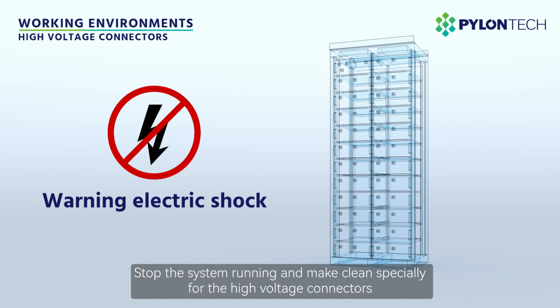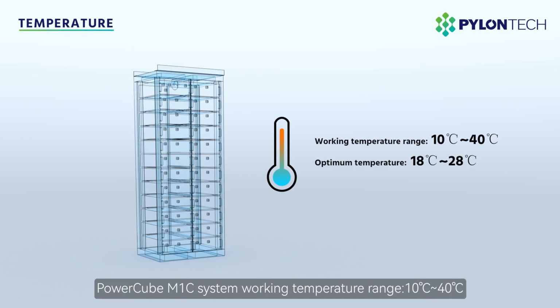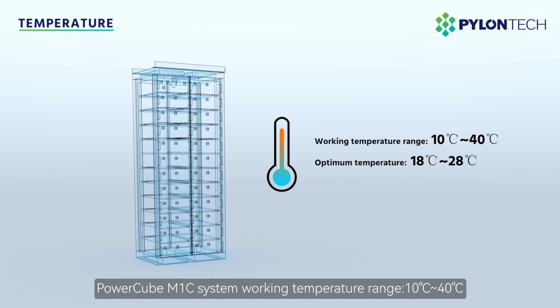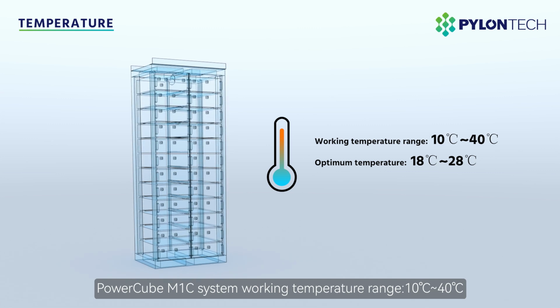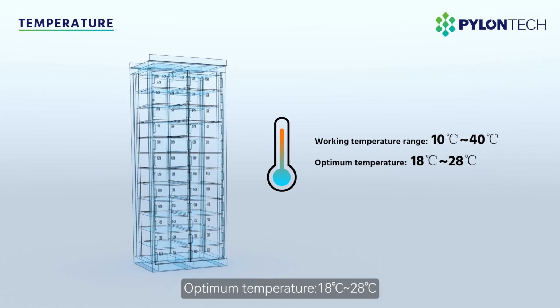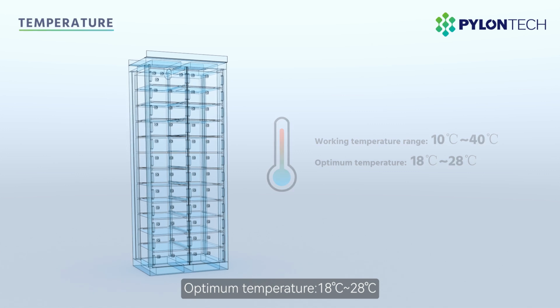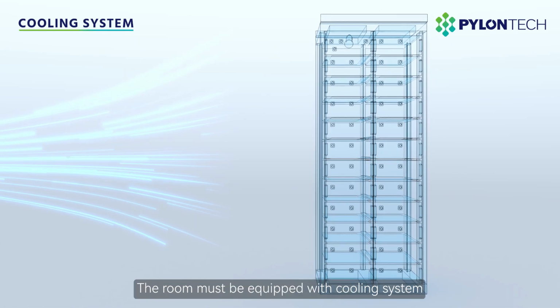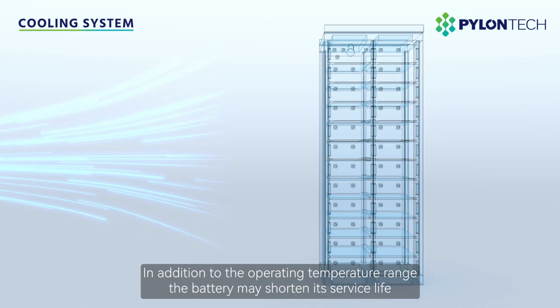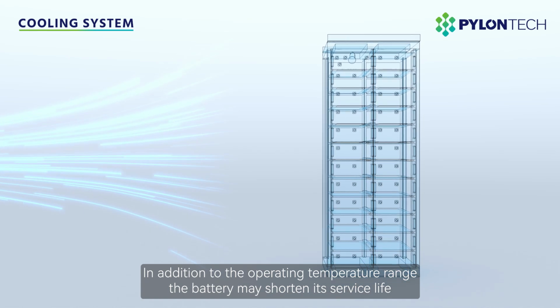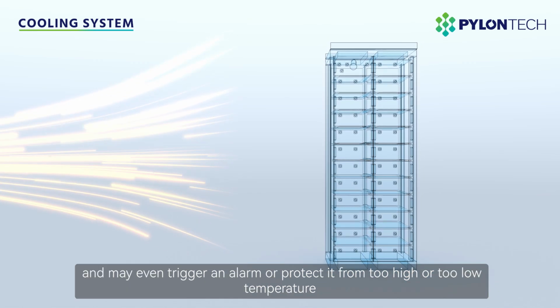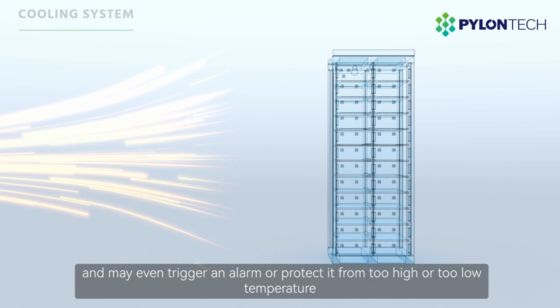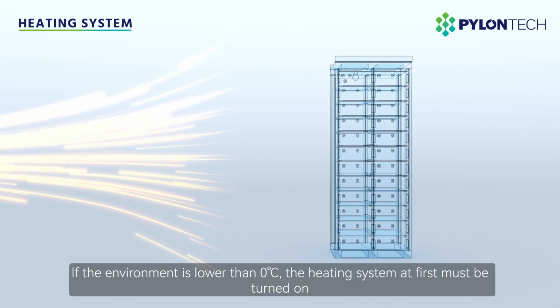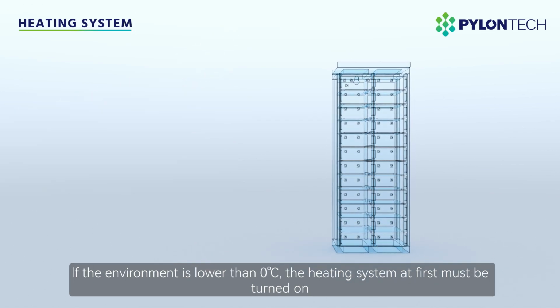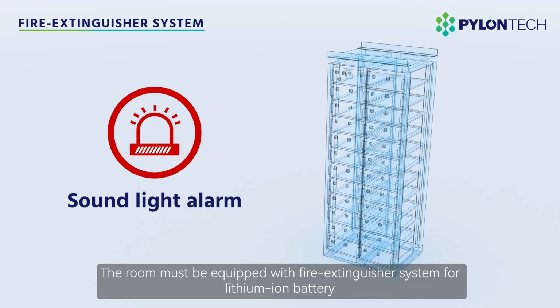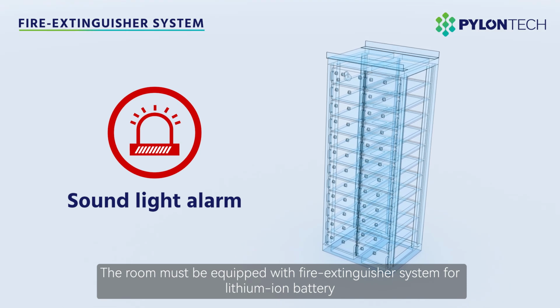high voltage connectors. PowerCube M1C system operating temperature range is 10 degrees Celsius to 40 degrees Celsius. Optimum temperature is 18 degrees Celsius to 28 degrees Celsius. The room must be equipped with a cooling system. Outside the operating temperature range, the battery may shorten its service life, and may even trigger an alarm or protect itself from too high or too low temperature. If the environment is lower than 0, the heating system must be turned on first. The room must be equipped with a fire extinguisher system for lithium-ion batteries.